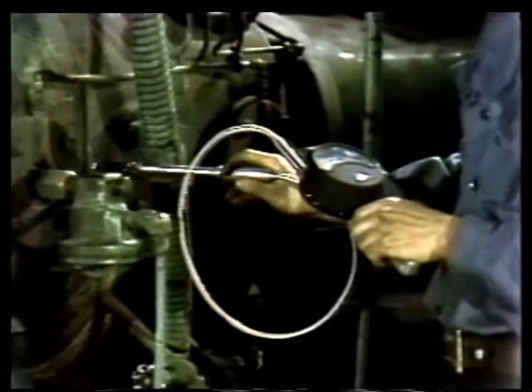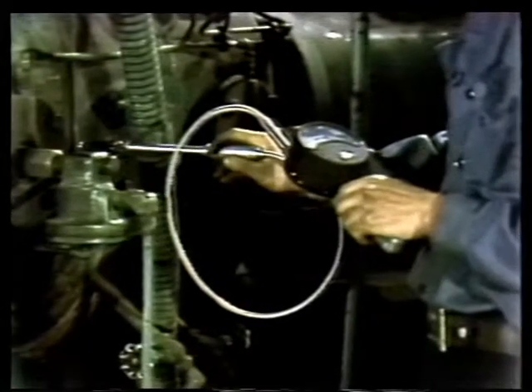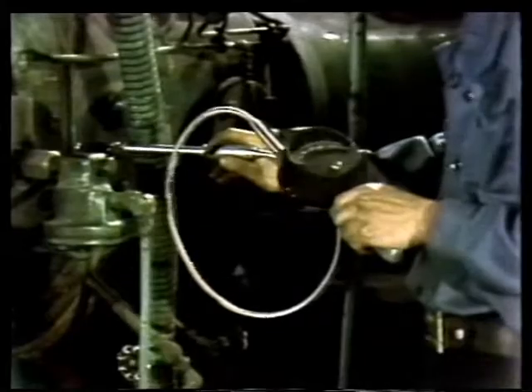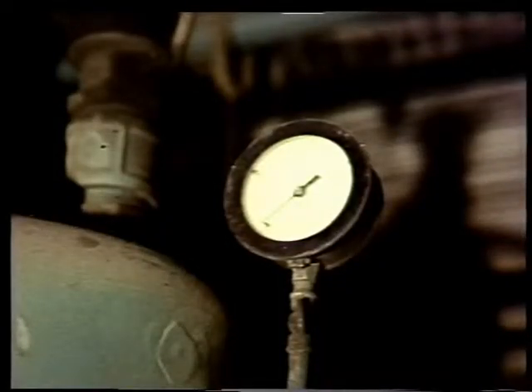Check for heat by feeling the valve or by using a pyrometer and comparing the reading to that of the other valves. A further check for a loose discharge valve could be the pressure of the discharge. If the valve is loose, the compressed air could leak back into the cylinder, causing the discharge pressure to be lower than normal. Be sure that you don't jump to conclusions. There are other reasons for a hot cylinder and a low discharge pressure. A worn piston or scored cylinder will also cause the cylinder temperature to go up and the discharge pressure to go down. But if the problem is a valve, only that valve will be hot and not the whole cylinder.